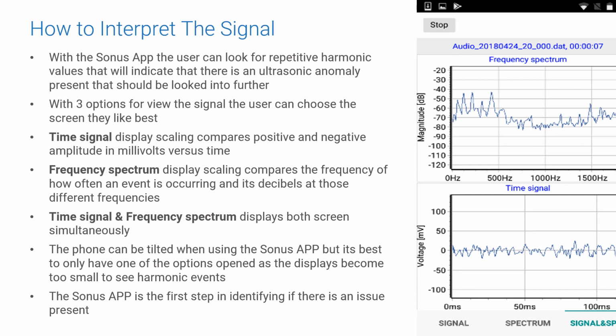Time signal is my preferred method of displaying the values being seen on the screen, where the display scaling compares positive and negative amplitudes in millivolts versus time. In frequency spectrum, the display scaling compares the frequency of how often an event is occurring and its decibels at those different frequency values. In a combined screen of time signal and frequency spectrum, both screens are displayed simultaneously. This makes the screens much smaller and harder to see. The recommendations from IRISS are to choose one of the 2 listed above as your single screen to view.